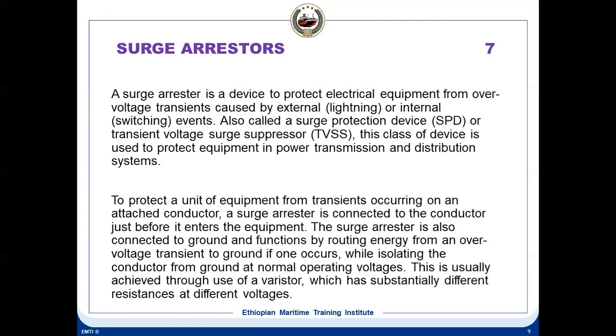A surge arrestor is a device to protect electrical equipment from over voltage transients caused by external or internal events, so switching times or lightning times. Whatever the surge is, to absorb or control that surge, we are using surge arresters. But in circuits and all, we are using varistors. A varistor is a semiconductor, it's like a resistance, but the property is that with variation in the voltage, the resistance varies. Like generator output and all, we are using varistors. So when spikes come, it will absorb the spikes.